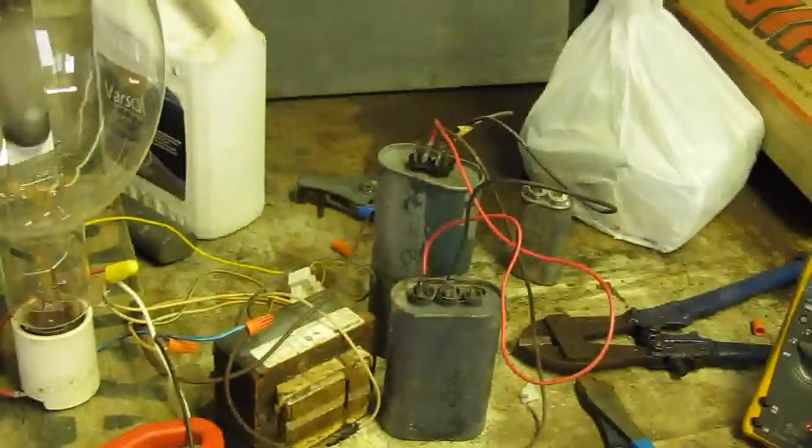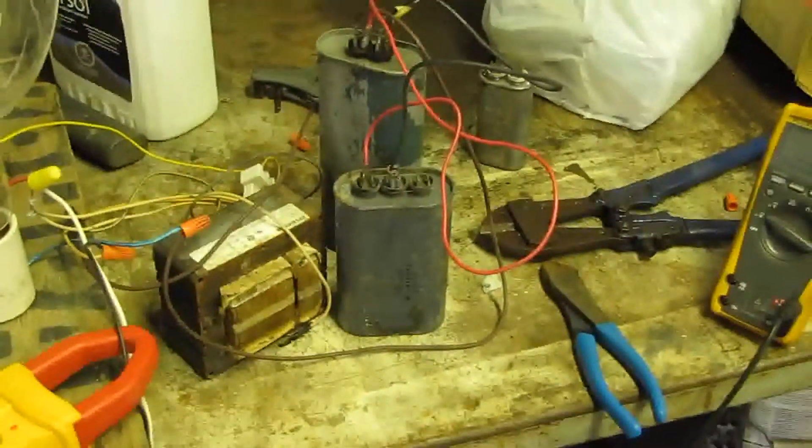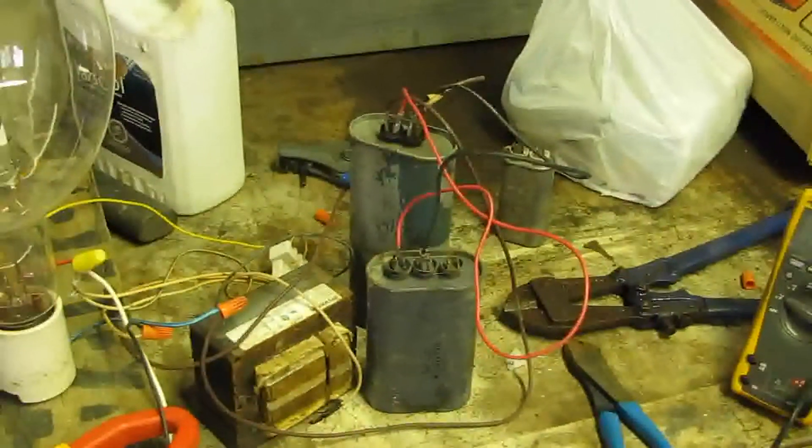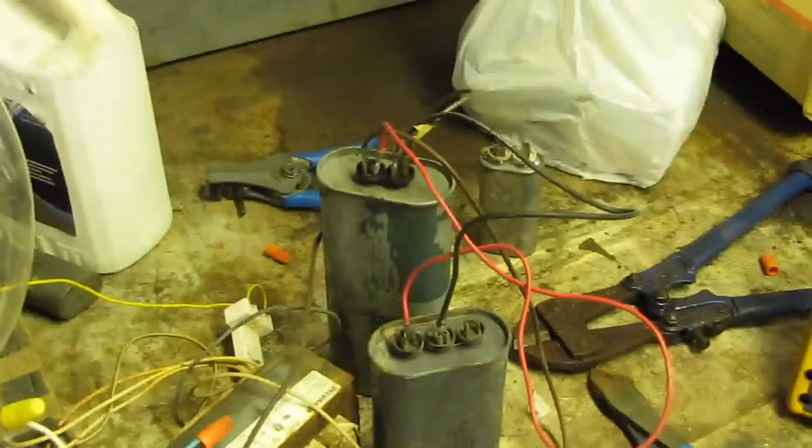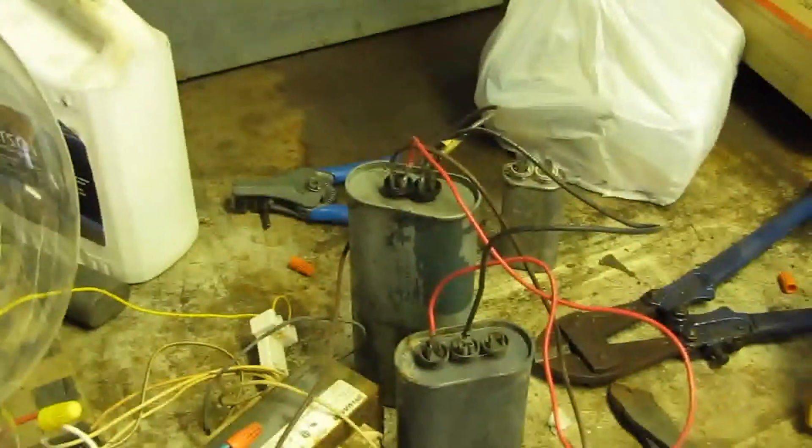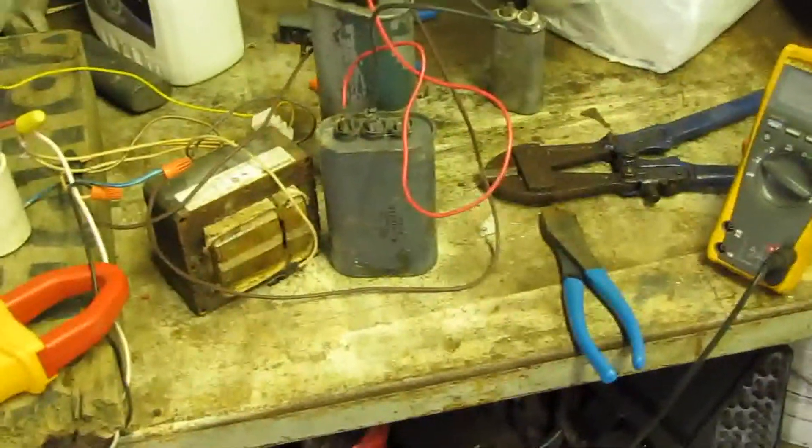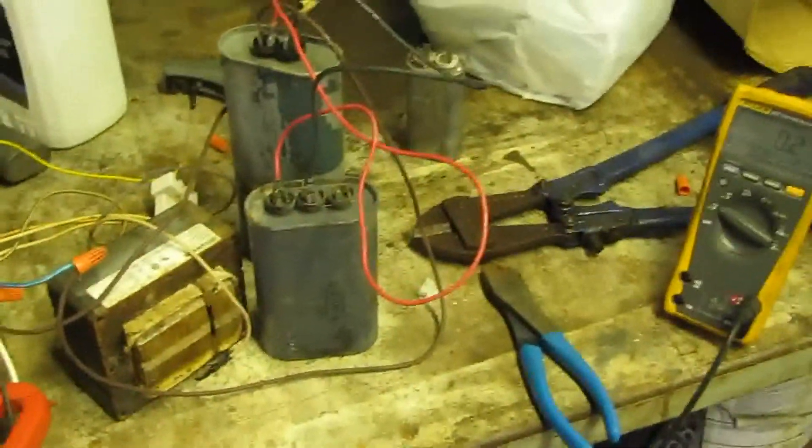I got two AC capacitors here, one's a split capacitor for running a big electric motor and a small one at the same time, generally found in an air conditioner. The other one's just a straight capacitor used to start big compressors in single phase motors. Their rating is 370 volts AC and the big one is 35 microfarad and the small one's split at 25 and 7.5.